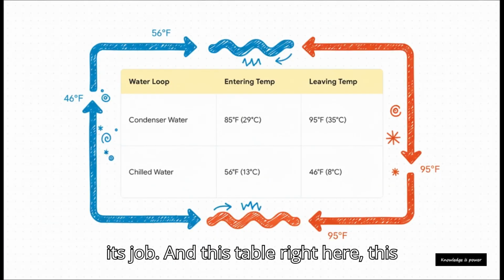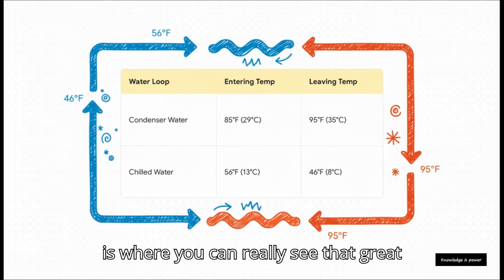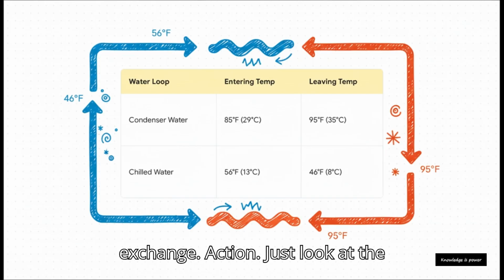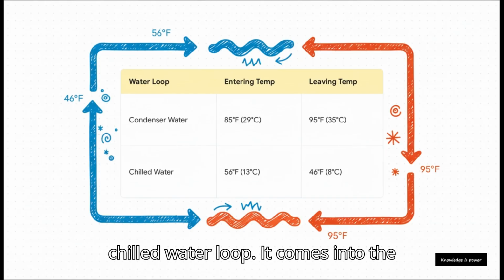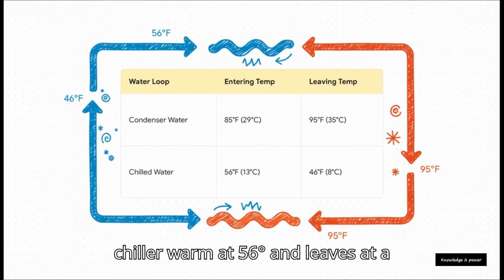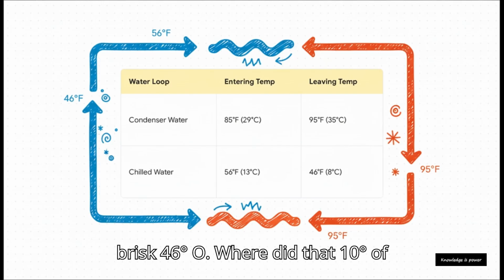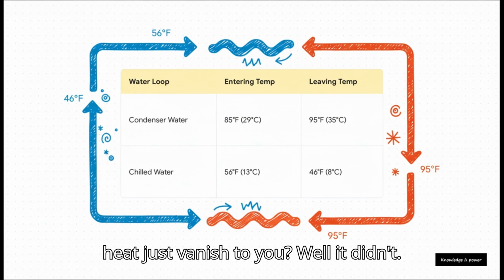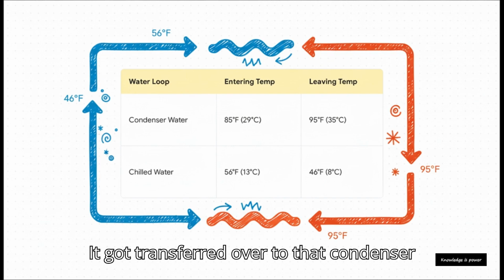This table right here is where you can really see that great exchange in action. Just look at the chilled water loop: it comes into the chiller warm at 56 degrees and leaves at a brisk 46 degrees. So where did that 10 degrees of heat just vanish to? Well, it didn't. It got transferred over to that condenser water loop.